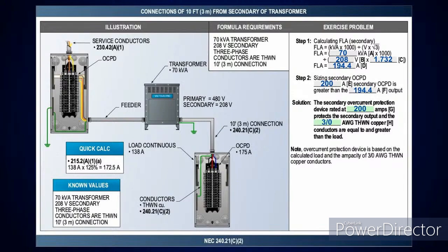Well, if I want to size the overcurrent device for that, I'll look at table 240.6(A) for the standard ampere rating. The next size above that is 200 amp. And then if I look at table 310.16, 75 degree C column, 200 amps is for a 3-aught conductor. So in this case, I sized it real quick: I need a 200 amp overcurrent device and 3-aught copper conductors.